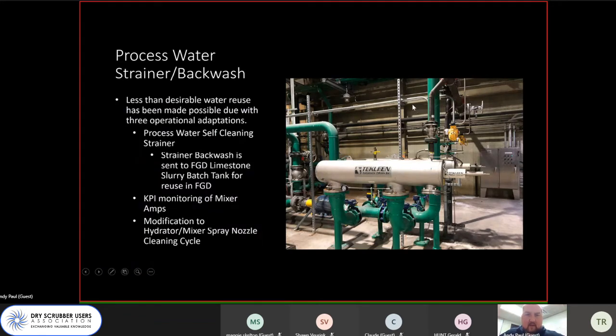So a couple things we did to optimize the materials we use, especially with cooling tower blowdown and warmer month operation: we installed self-cleaning strainers, and this has been a big piece for us. We're able to use water with higher suspended solids and filtrate it. Then we take the backwash water from this and put it in our Unit 3 limestone slurry tank that feeds the Unit 3 FGD. So we're able to reuse all of that water internally without adding additional surface water to the system.